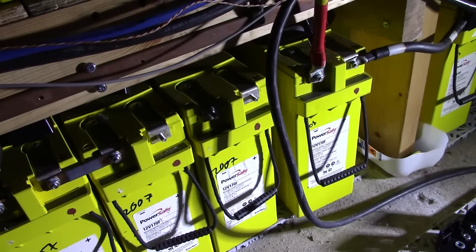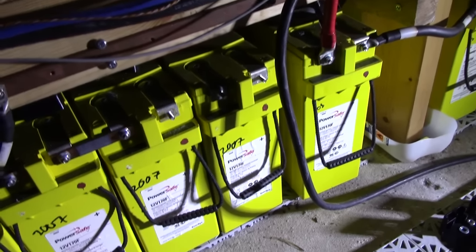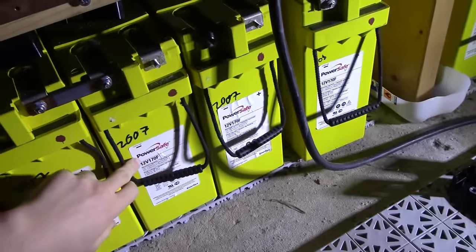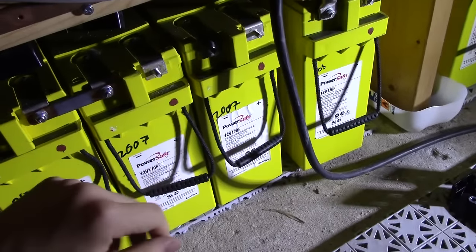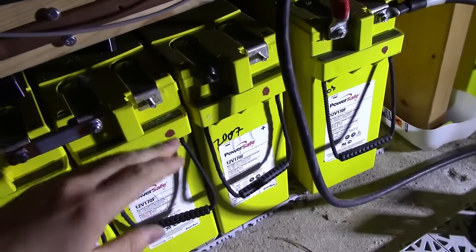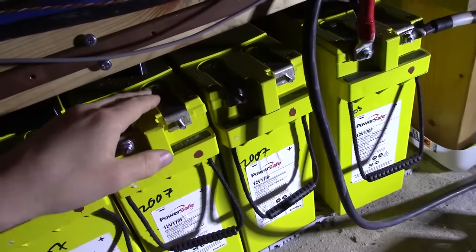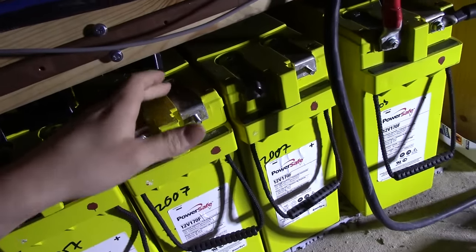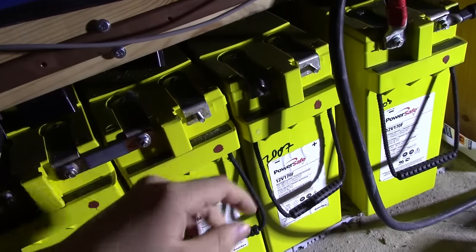Because I'm not sure if I ever mentioned it in a video, but all these semi-old Power-Safe batteries, a lot of them have issues where electrolyte will start leaking out underneath these little busbar connection thingies.